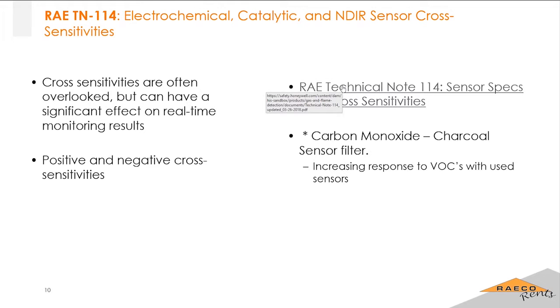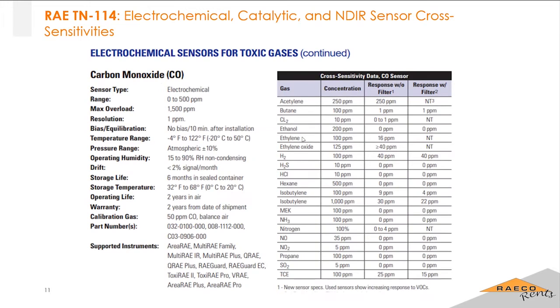Another important thing to look at is cross sensitivities on sensors. These are electrochemical sensors, and they can respond to other gases, so you can get false readings. There are both positive and negative cross sensitivities, so it goes both ways. There's a good technical note, a clickable link in the PowerPoint, that gives an example for carbon monoxide, the most basic sensor we have. It doesn't have too many large cross sensitivities.